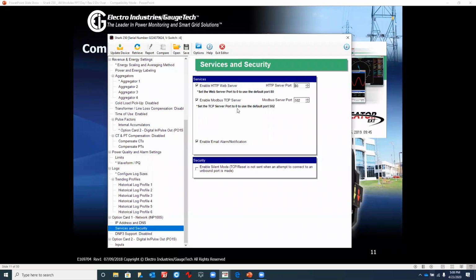The Modbus TCP server, you want to enable that so you can do Modbus polling. And again, the default TCP port number for Modbus is 502, although you have the ability to change that to any other port number, especially if you're doing port forwarding. It's something that you want to be able to change those port numbers. The next is enable email notification. You want to enable that if you want to make use of that feature, which I'll discuss on the second day of the presentation.